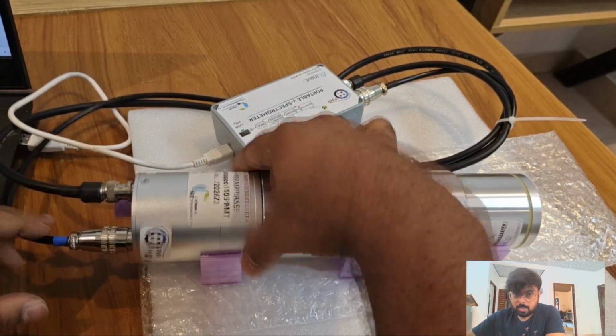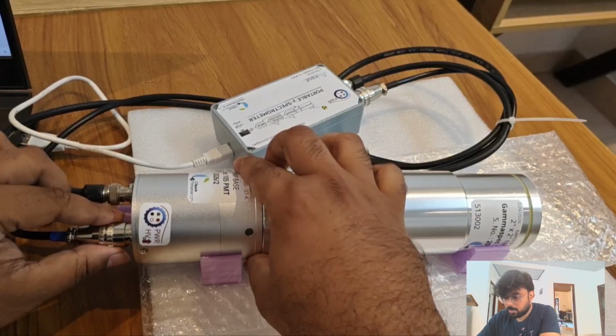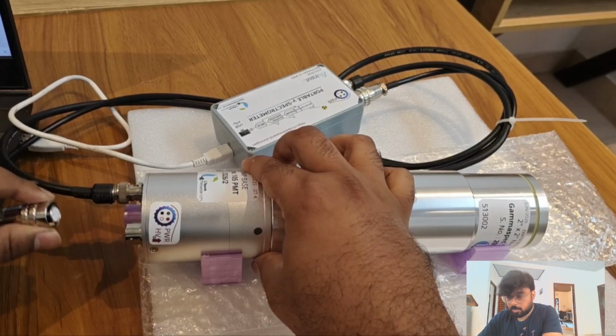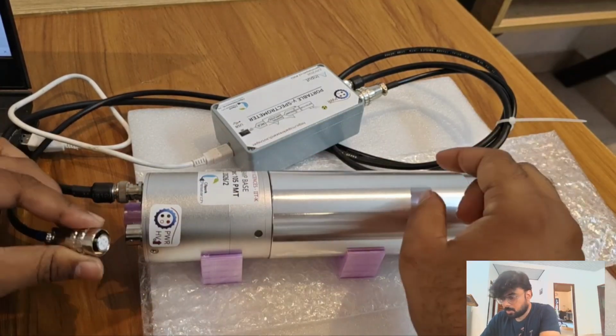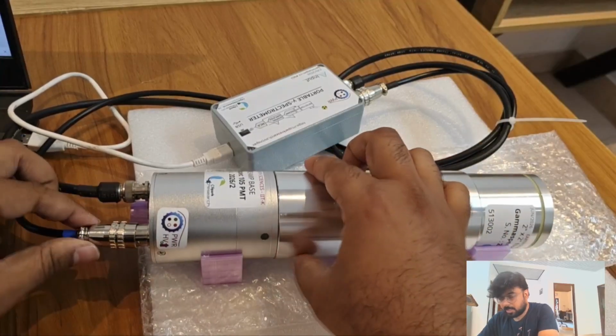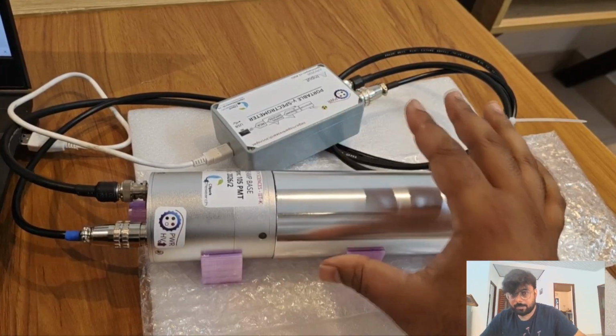And the power supply, HV, etc. comes in through here. So this is an aviation type connector, which means you just hold this and pull, so do not twist, and put it back in. There is a notch here, so just be careful to align the notch. Once that notch is in place, you'll be able to just push it back in place.